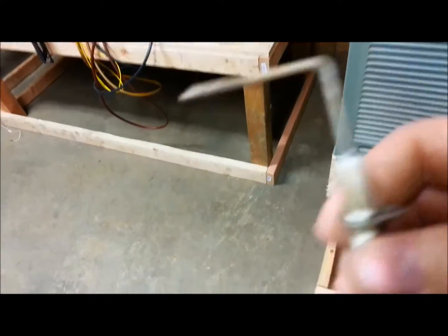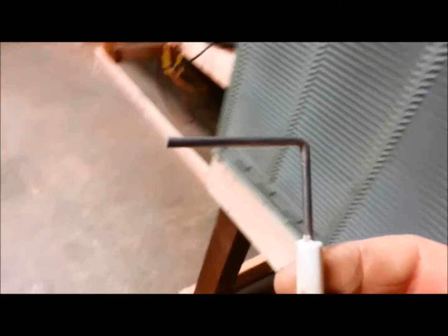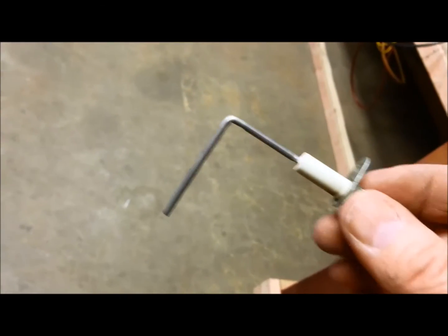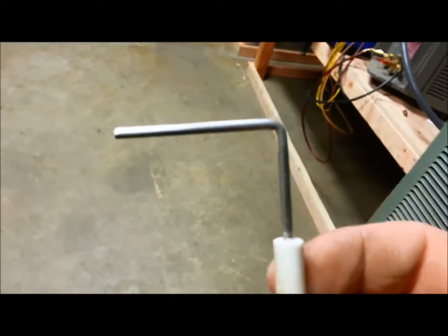Okay, I've cleaned the flame sensor. It's nice and polished now. You can see how shiny it is. We should get a better flame sense now, so we should be able to see a lot better reading, a higher reading, so that we don't have this thing shutting off because we're not getting good flame rectification through there and allowing current to flow.